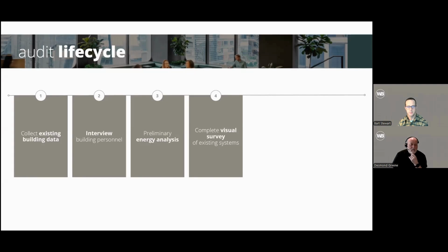We establish how the building operates - current facilities requirements, a document that outlines the current specifications for a building, including temperature set points, relative humidity, operating hours, levels of filtration, and pressurization requirements for each space. If you don't have a CFR, current facilities requirement, you can easily put one together, or we can do this as part of the audit.